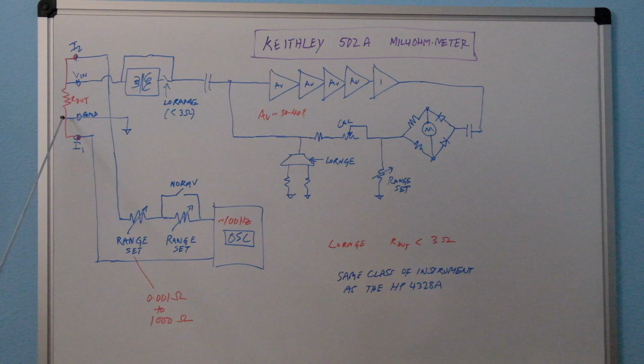So, and there's the final stage, which is the unity gain that drives the DC blocking cap, and the current is flowing through this meter, which is a 50 microamp sensitivity meter. And this calibration is for setting the full scale, or a certain scale actually, not full scale. In this case it's 0.7 times full scale. And there are other bypass resistances for when you want to change the range. Some of these currents are bypassed so that you don't overrange the meter. So these are resistances used for that, and that is part of the rotary switch that controls a lot of these range functions. So as I mentioned, the low range is below 3 ohms, and it goes on to 0.001 ohm, 0.003, 0.01, and so on, all the way up to 1K.